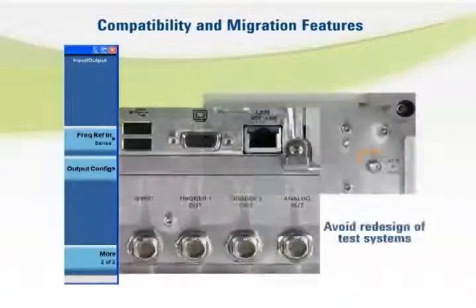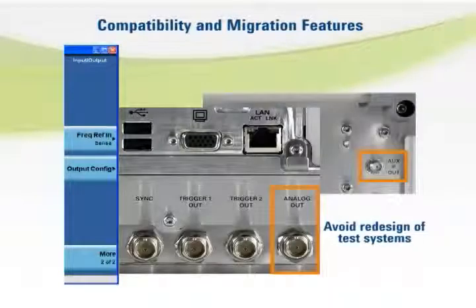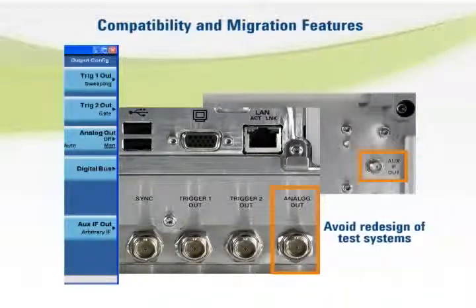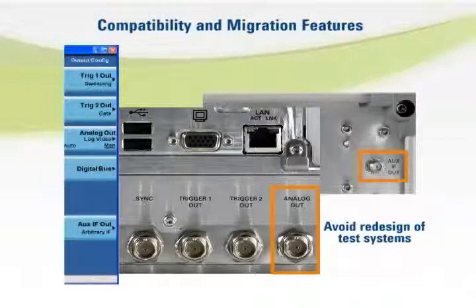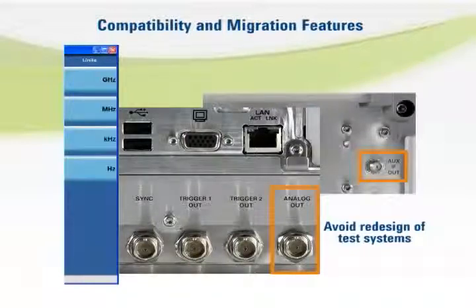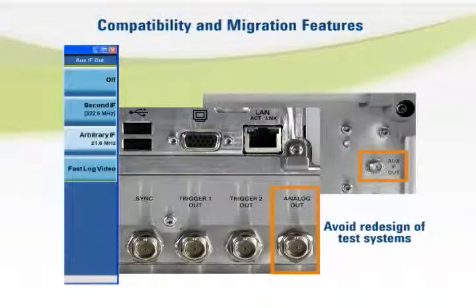A range of hardware features, including fast rise time video out, Y-axis video output, and an innovative variable frequency IF output, minimize the need to redesign test systems when migrating to the PXA. This compatibility enables you to accelerate tests, increase throughput, and reduce the number of test stations.